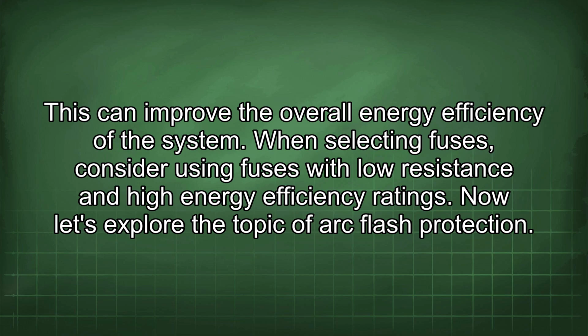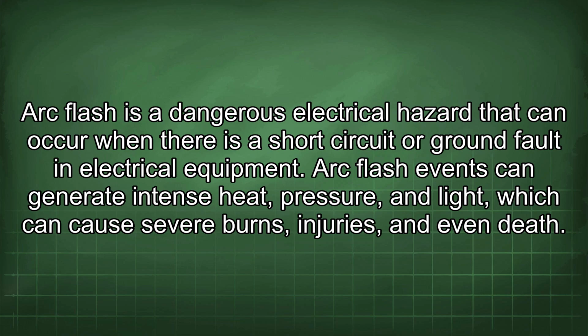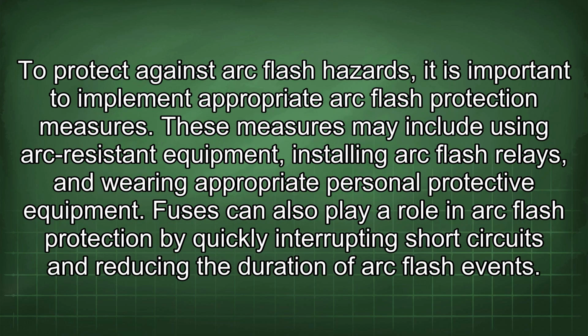Now let's explore the topic of arc flash protection. Arc flash is a dangerous electrical hazard that can occur when there is a short circuit or ground fault in electrical equipment. Arc flash events can generate intense heat, pressure, and light, which can cause severe burns, injuries, and even death. To protect against arc flash hazards, it is important to implement appropriate arc flash protection measures. These measures may include using arc-resistant equipment, installing arc flash relays, and wearing appropriate personal protective equipment.